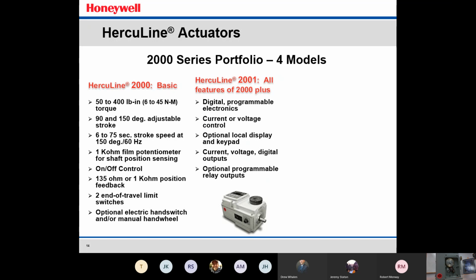So the digital outputs would be coming from your control system to the actuator to control it. And then there are optional programmable relay outputs in addition to the solid state outputs that are on the actuator. So if you had a display that was hooked up to this model, you could configure your outputs for position output, current input. You could configure it for diagnostics that are inside the recorder, like high temperature, for example, or repositions. So there's a lot of different ways you can configure these relay outputs on this particular model to give you some enhanced insight into what the actuator is doing.